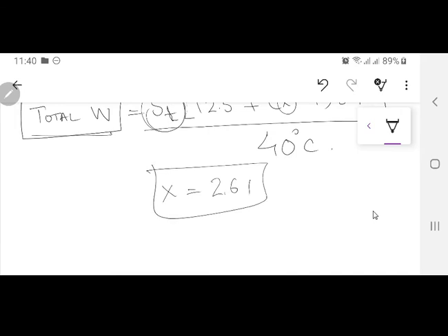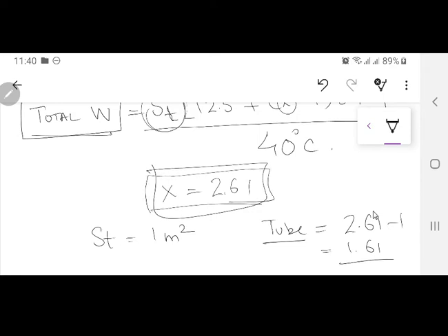2.61 means if you have ST equal to 1 meter square, then the area of your tubes will be equal to 2.61 minus 1 meter square. I'm just giving an example, solving it numerically, where using the above formula x comes out to be 2.61, which is 2.61 minus 1 meter square, the area required for the tubes.